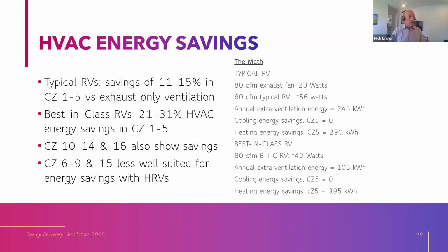We also showed savings in 10 through 14 and 16. 16 is the Sierras, 10 through 14 is the Inland Empire and Central Valley. And 6 through 9, the coastal Southern California -- Santa Barbara down to San Diego, Irvine, LA, Palm Springs -- less well suited for these typical heat recovery ventilators. I'll show you the math there: there's extra ventilation energy that kind of cancels out the heating or cooling energy savings to some extent.